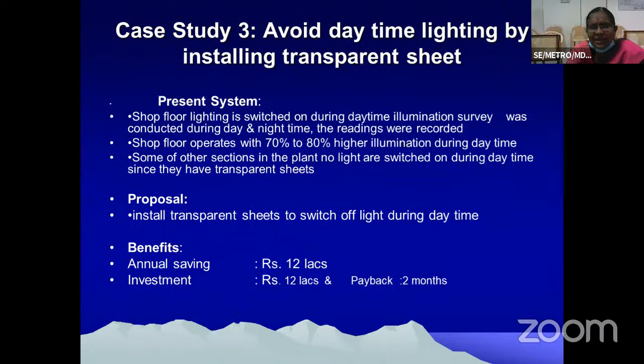Avoid daytime lighting by installing transparent sheet. This also they can implement in all the industries. Shop floor lighting is switched on during daytime. An illumination survey was conducted during day and night time. The readings were recorded. The shop floor operates with 70% to 80% higher illumination during the daytime. In some other sections of the plant, no lights are switched on during daytime since they have transparent sheet. So they have proposed to install transparent sheet to switch off the light during the daytime. Annual saving was 12 lakhs. Investment 12 lakhs. Payback period was around 2 months.